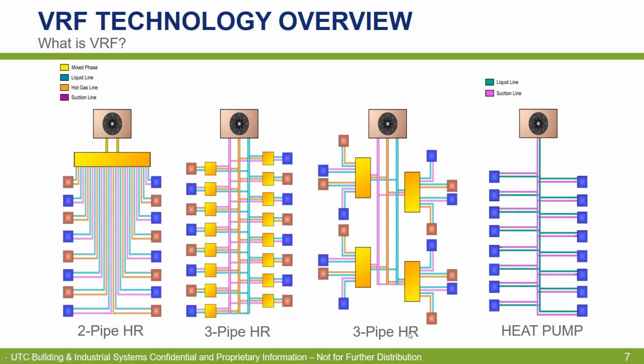Another diagram of a 3-pipe heat recovery system is where we have larger flow selectors. In this case, this would be representative of a 4-port flow selector. 1, 2, 3, 4. Also, larger flow selectors are available with the TOSHIBA-Carrier, in particular the 4 and the 6.